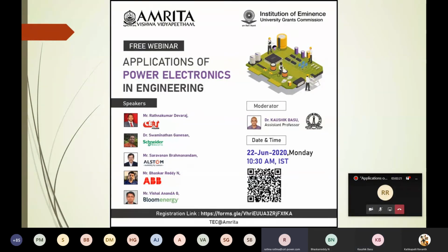Then we try to explain to them: go with our inverter. What is inside the box of TSI is an AC conversion, which is nothing but a double conversion taking place inside. So you have a DC buffer inside. In this case, what we try to tell the telecom operators is that you use the DC which is existing in the telecom center, so there is no need for an external DC bank to be incorporated like in the case of UPS.